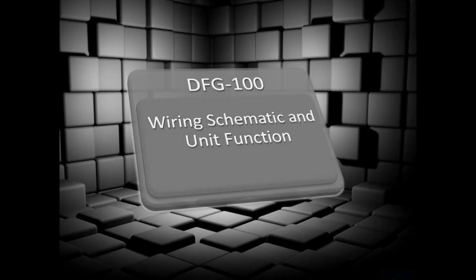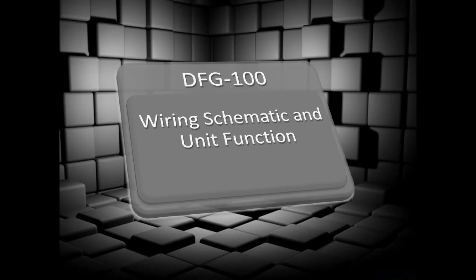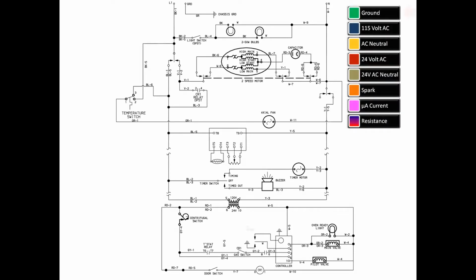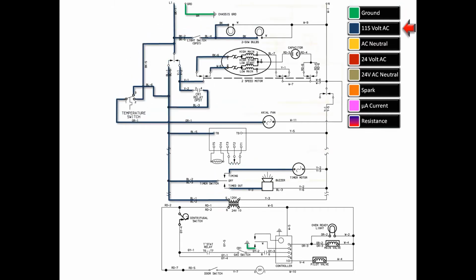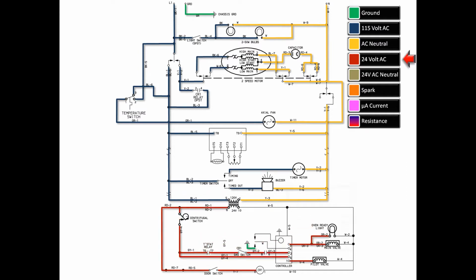In this segment, we will view the DFG-100 wiring schematic and see the components of the unit in action, while the different features of the unit are operated. The following electrical signals are present: ground, 115 volts AC, AC neutral, 24 volts AC, 24 volts AC neutral, high voltage spark, flame rectifying microamp current, and the resistance of the potentiometer and probe.